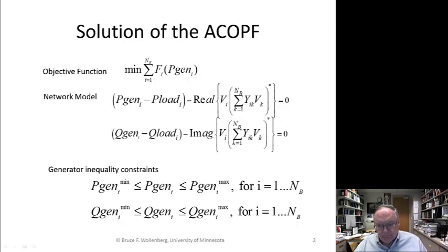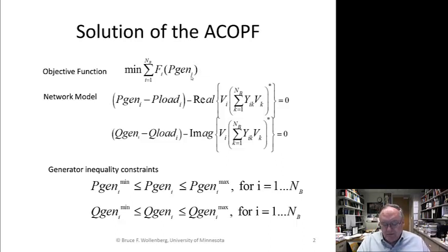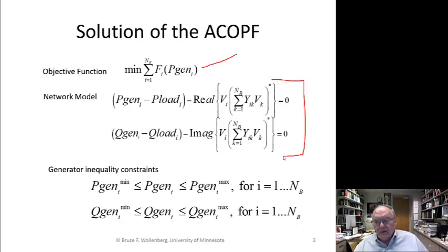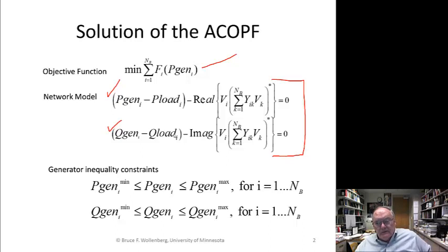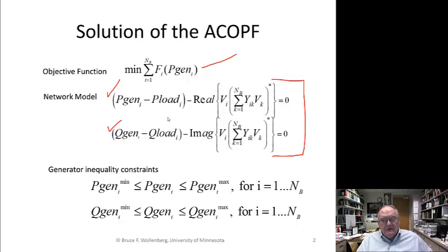We said that first we're going to have the same objective again: the minimum of the sum of the operating costs. Then we have our AC power equations — one equation for real power and one for reactive power for every bus. So there are two equations per bus, except for the reference bus. The reference bus voltage magnitude and phase angle are considered constants.